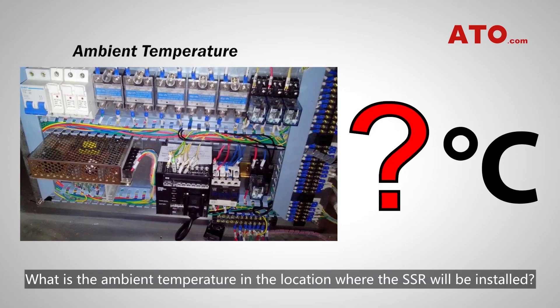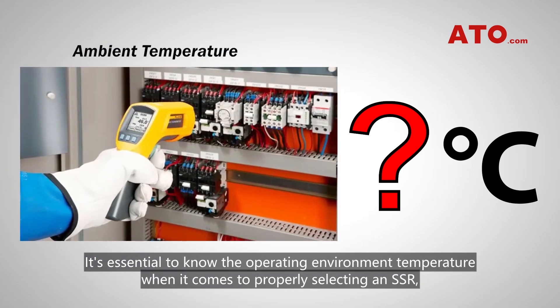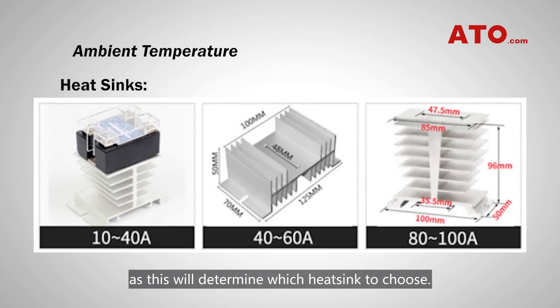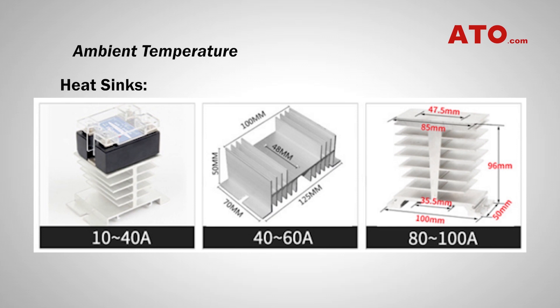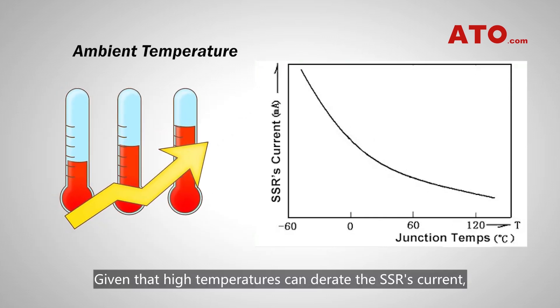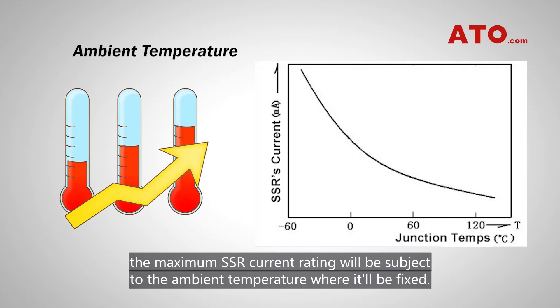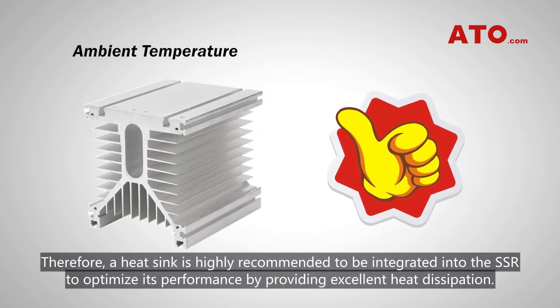Number 6: Mind the ambient temperature. What is the ambient temperature in the location where the SSR will be installed? It's essential to know the operating environment temperature when it comes to properly selecting an SSR, as this will determine which heat sink to choose. Given that high temperatures can derate the SSR's current, the maximum SSR current rating will be subject to the ambient temperature where it will be fixed. Therefore, a heat sink is highly recommended to be integrated into the SSR to optimize its performance by providing excellent heat dissipation.